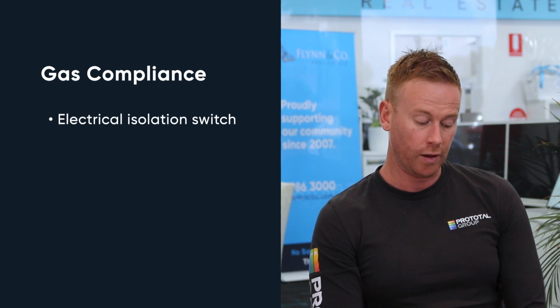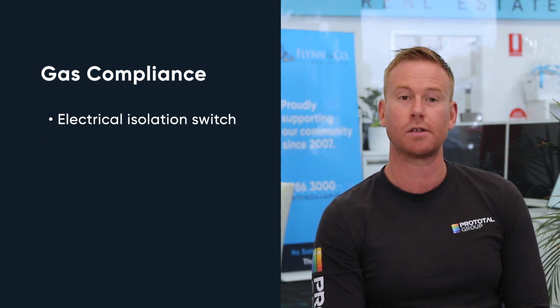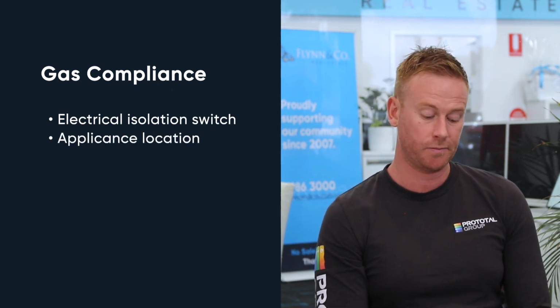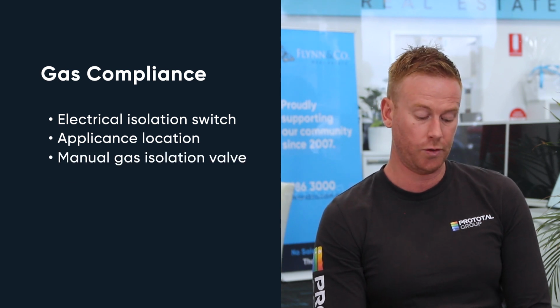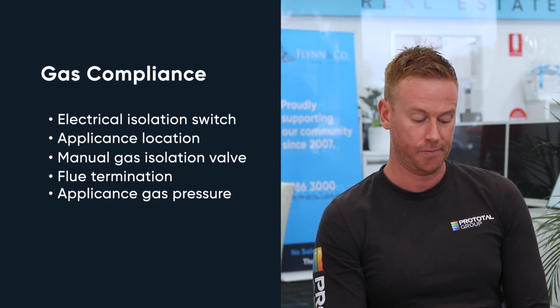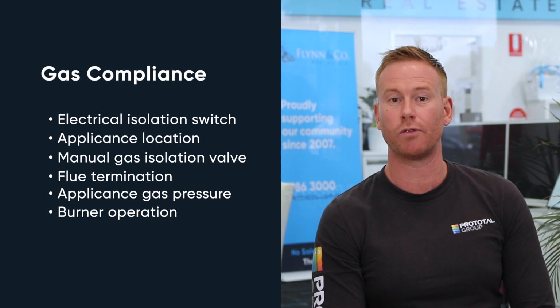And in relation to carbon monoxide testing, there are a number of tests that we need to do in sequence to ensure that your tenants are safe and, most of all, you're protecting your investment. We check for electrical isolation switches, correct appliance location, manual gas isolation valves, flue terminations, correct test pressure at your appliances, burner operation, and most of all, that there's a safety shutoff device operational.